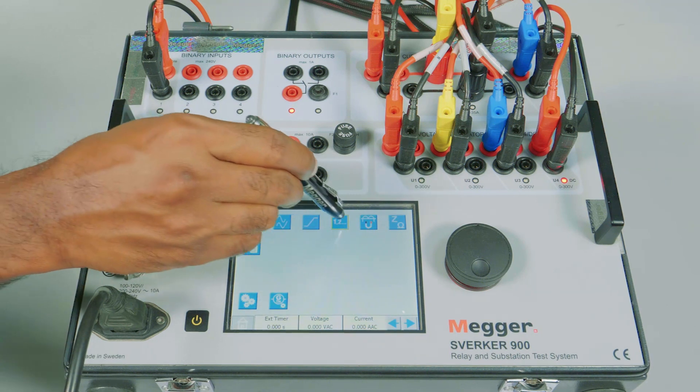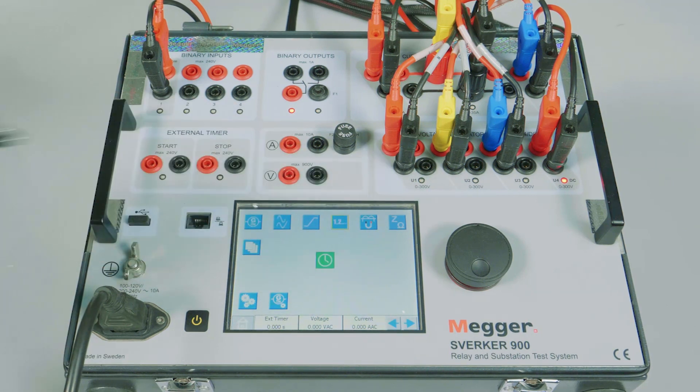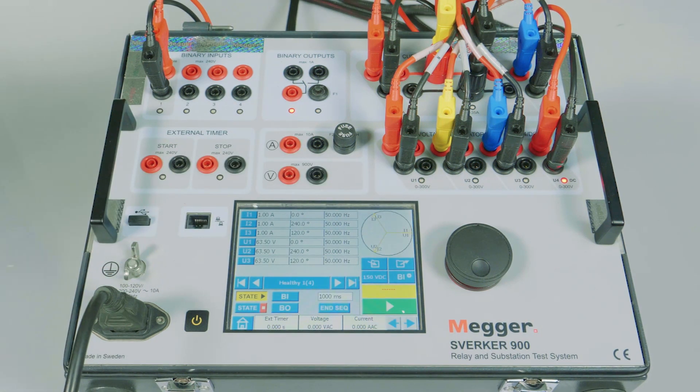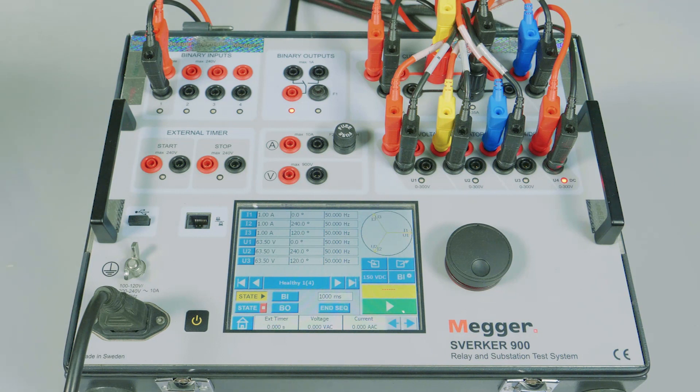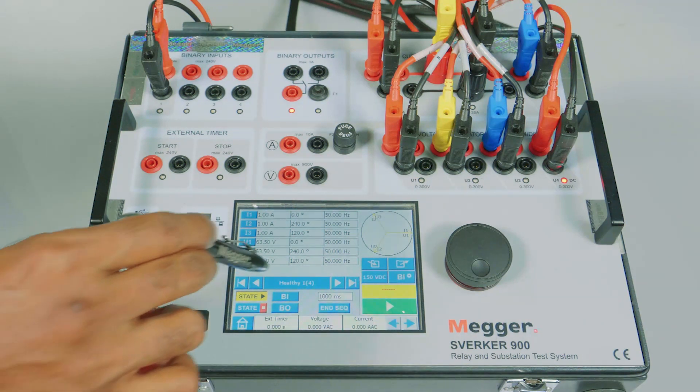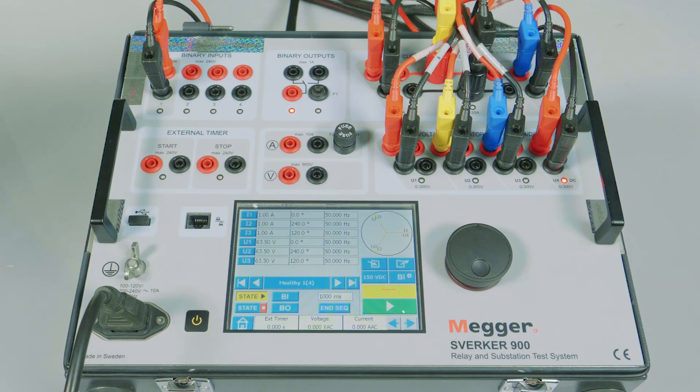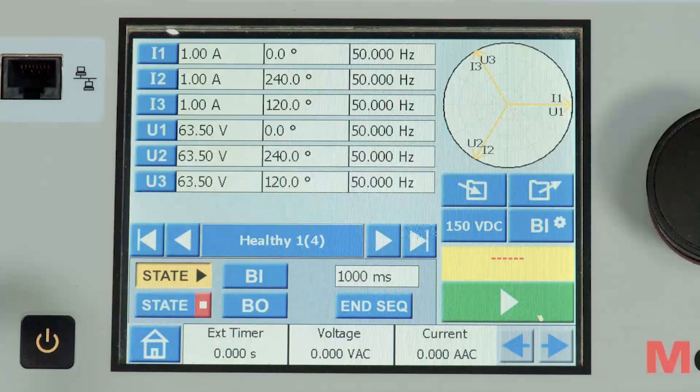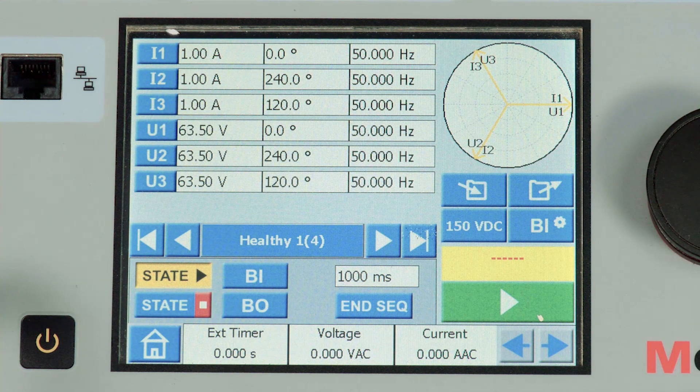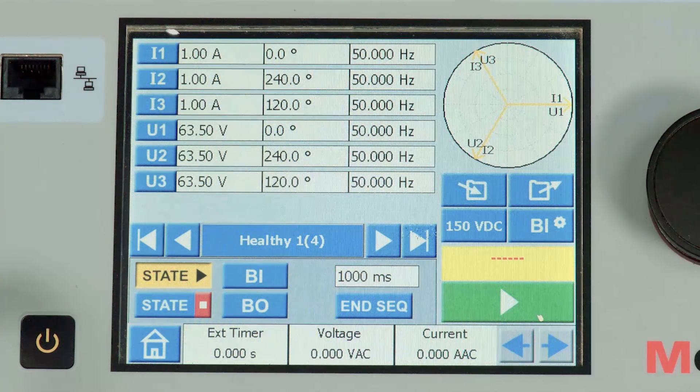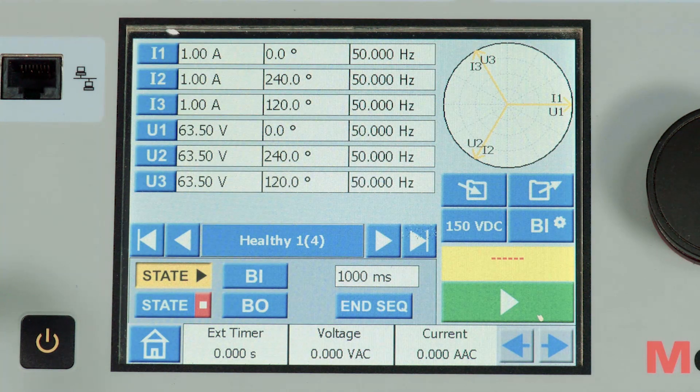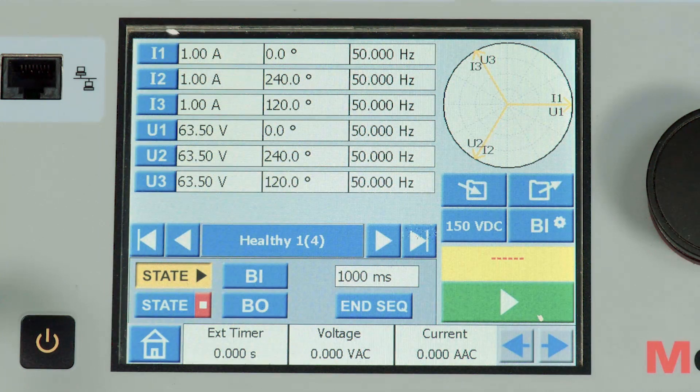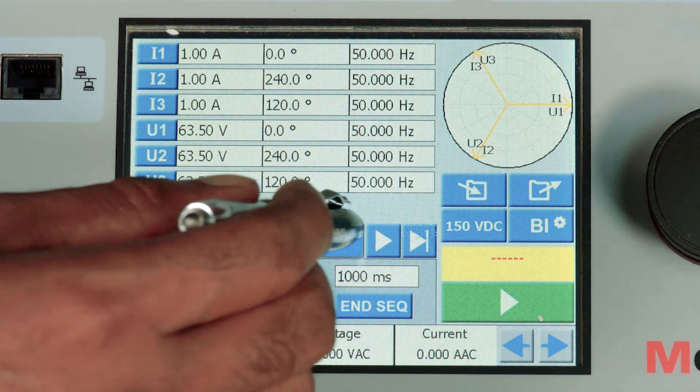To simulate an auto recloser let me open the state sequencing module. I have already configured the states. The first state is a healthy state configured for 1000 milliseconds with healthy current and voltage, 63.5 volts in all phases with balanced phase angle and 1 amp load current in all phases with balanced phase angle.